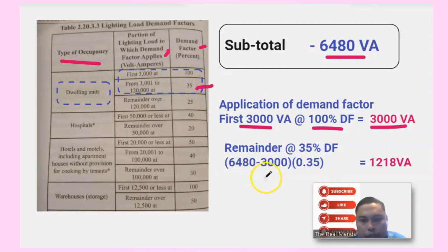So 6,480 minus 3,000, multiply mo siya ng 0.35, so we have 1,218 VA. So let's use this value for our calculations. Okay, so 3,000 and then remainder niya is 1,218 VA.